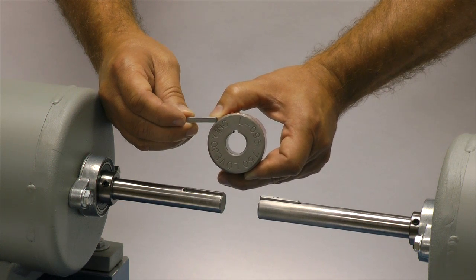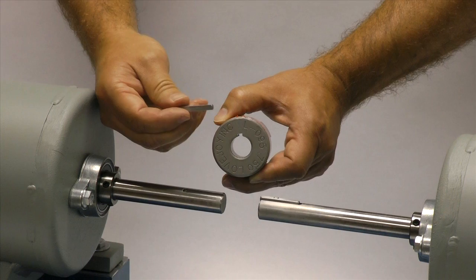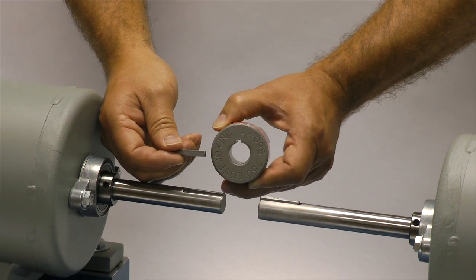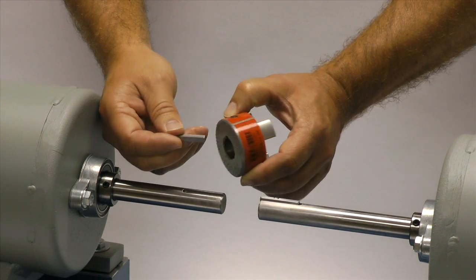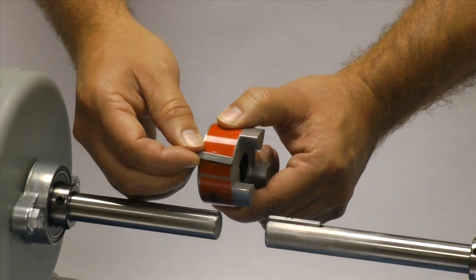If the shaft and the hub both have keyways, make sure you have the appropriate key ready to use when performing this installation. Ideally the key should be the same length or slightly longer than the hub to transmit the maximum allowable torque.